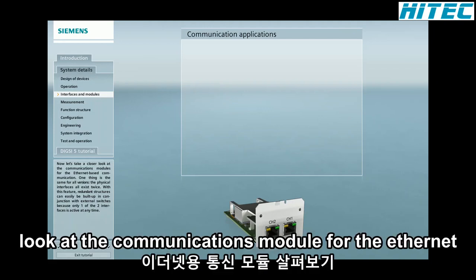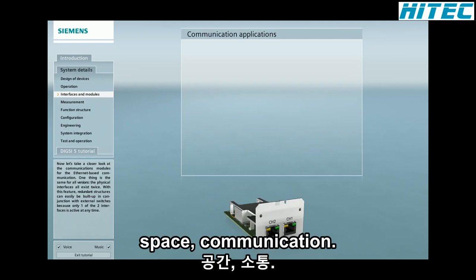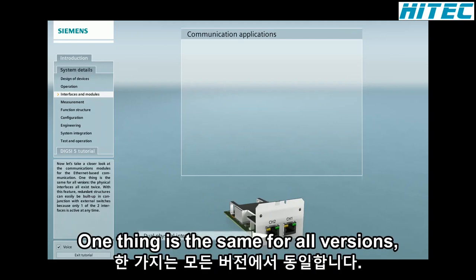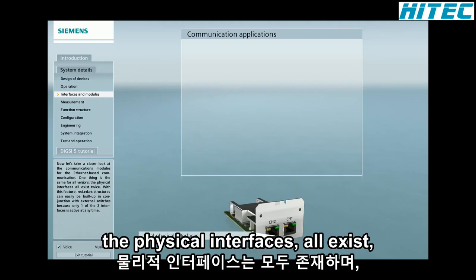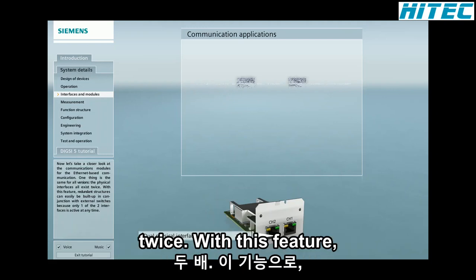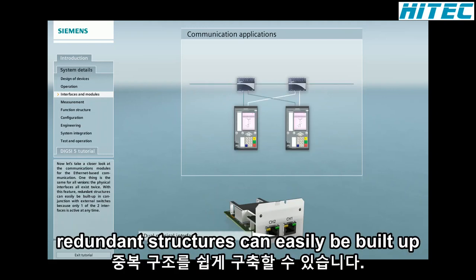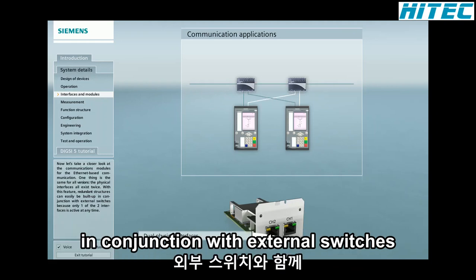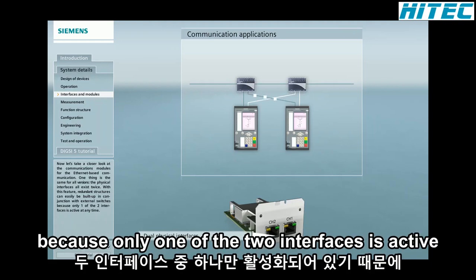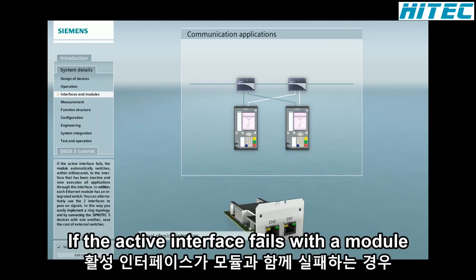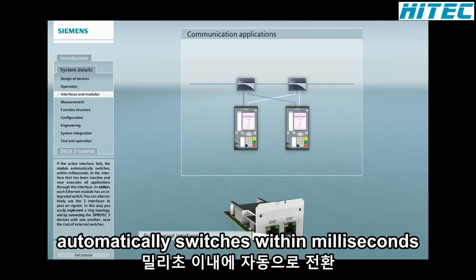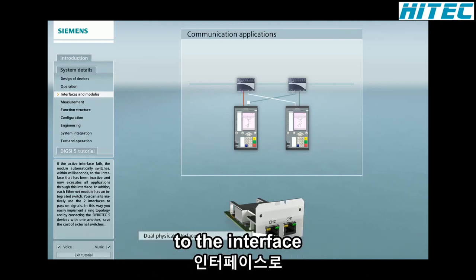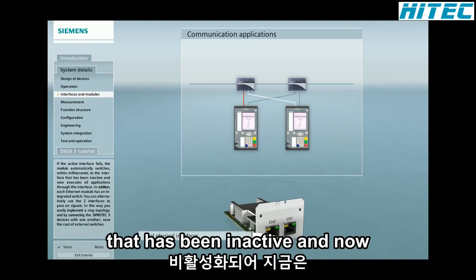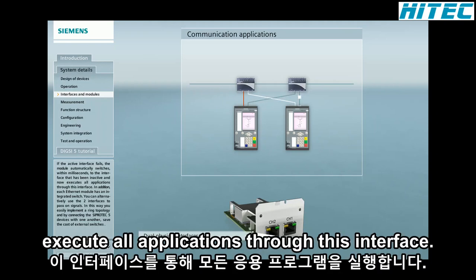Now let's take a closer look at the communications modules for the Ethernet-based communication. One thing is the same for all versions. The physical interfaces all exist twice. With this feature, redundant structures can easily be built up in conjunction with external switches because only one of the 2 interfaces is active at any time. If the active interface fails, the module automatically switches within milliseconds to the interface that has been inactive and now executes all applications through this interface.